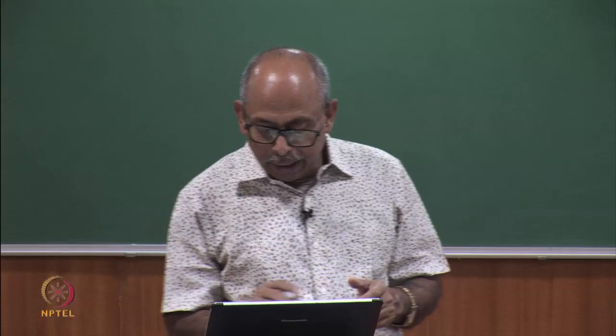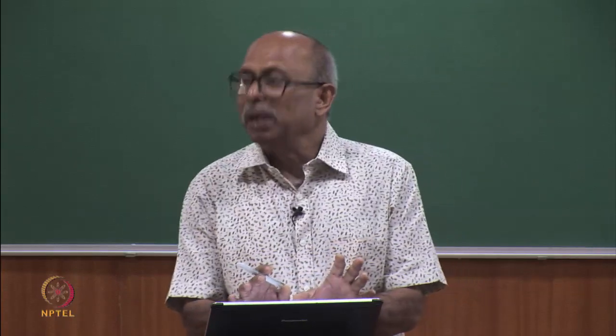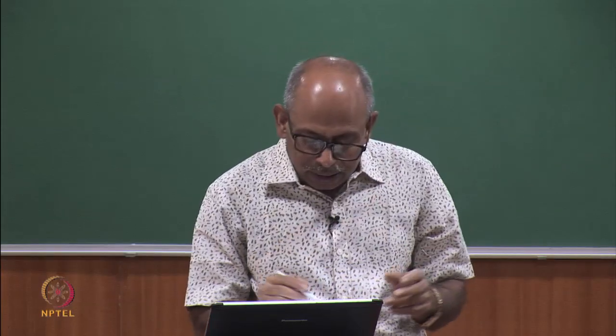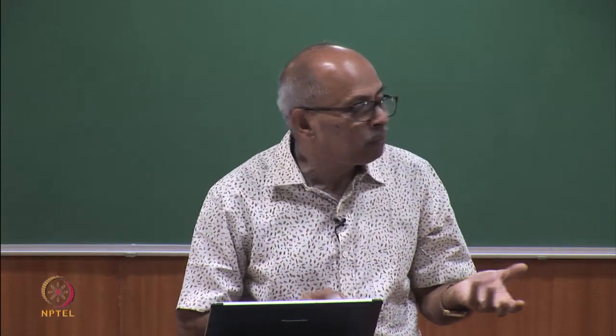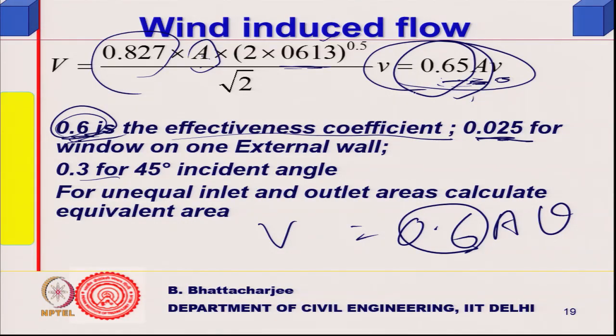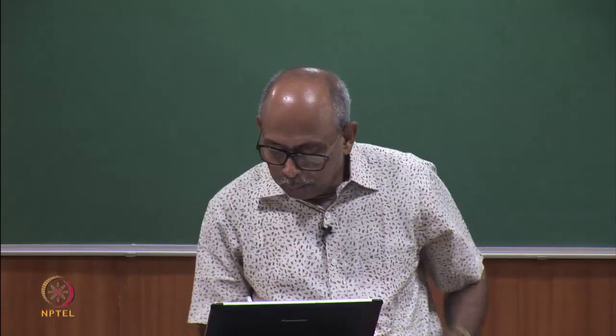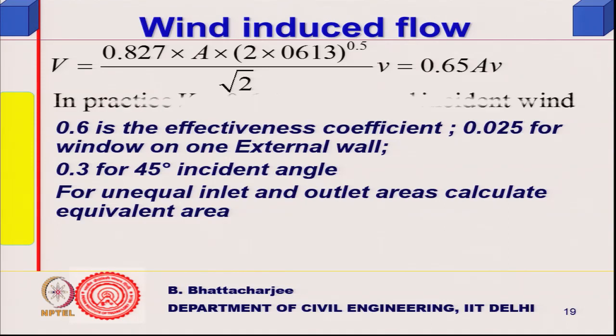For unequal inlet and outlet areas we can actually calculate the equivalent area — no empirical compromise there. However, this coefficient of effectiveness is somewhat empirical. The outside velocity at the window is not exactly the same as the free-stream outside velocity, which is why the coefficient is empirical, though its basis is clear.